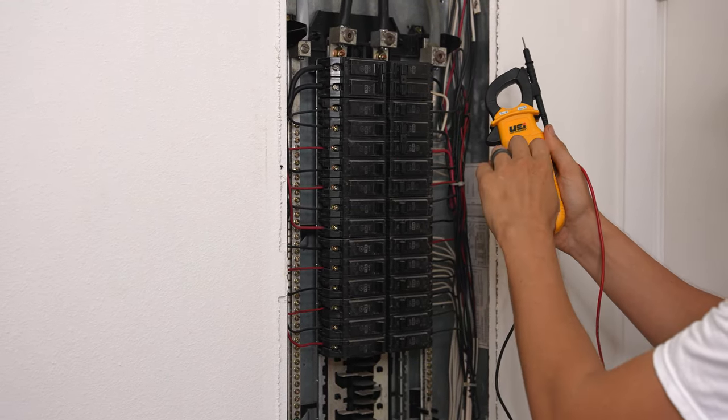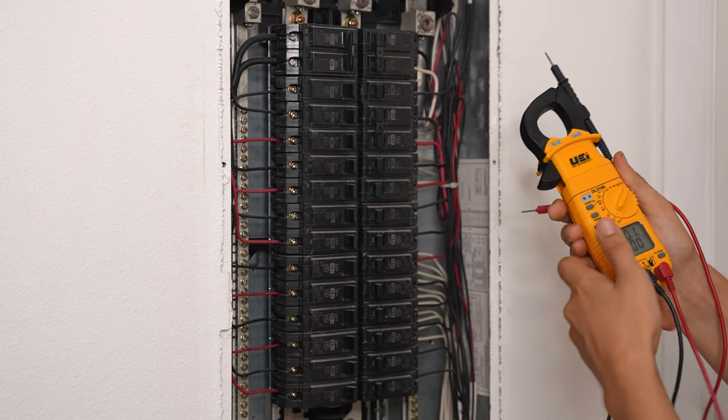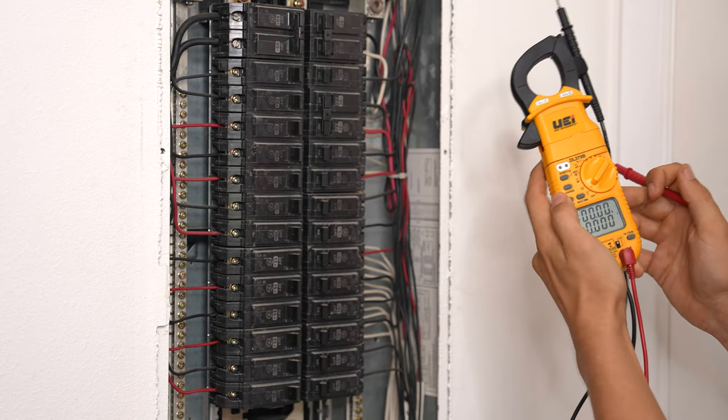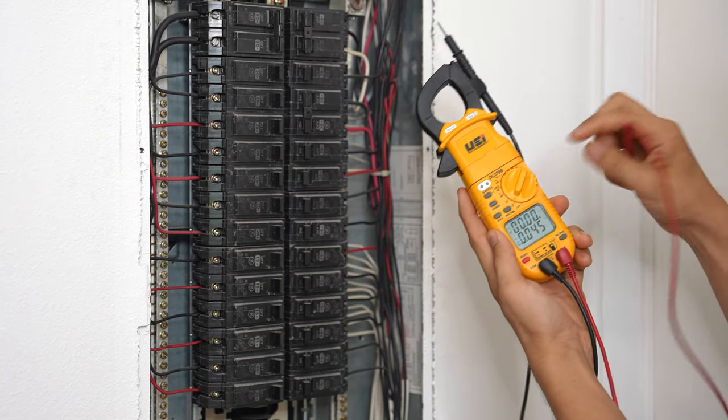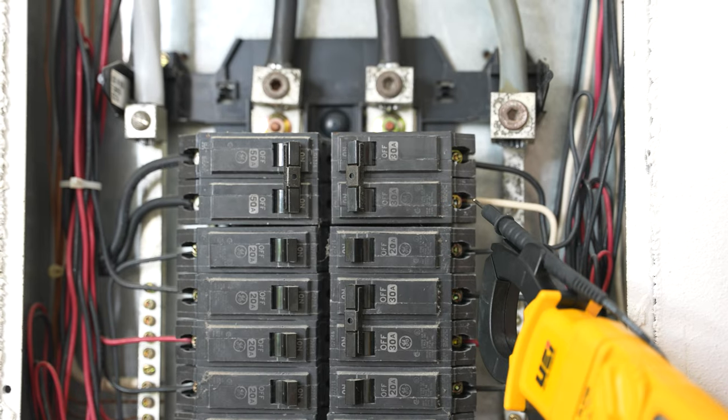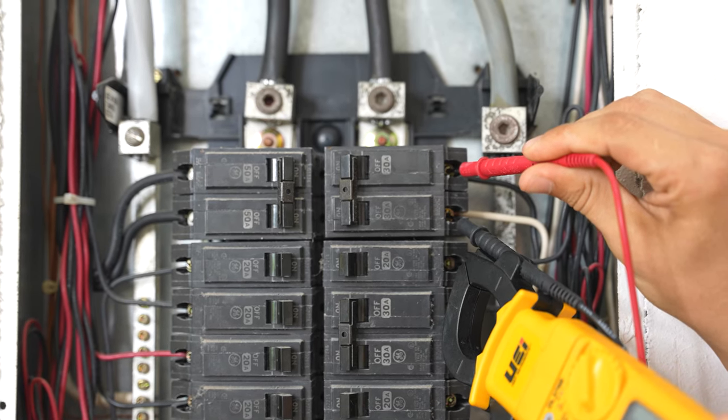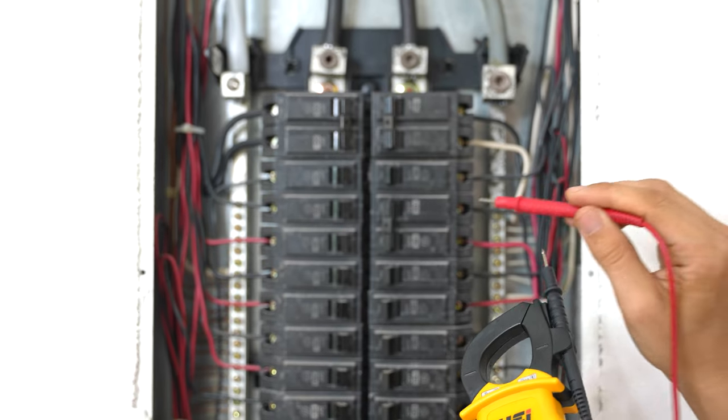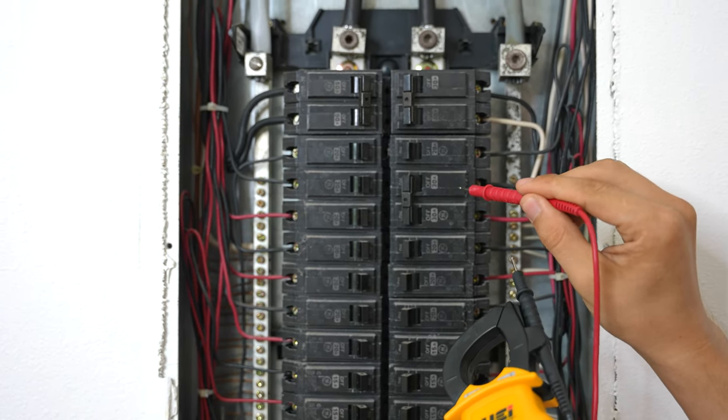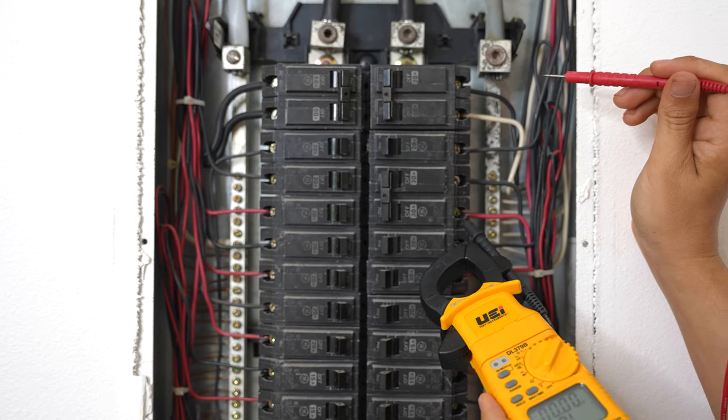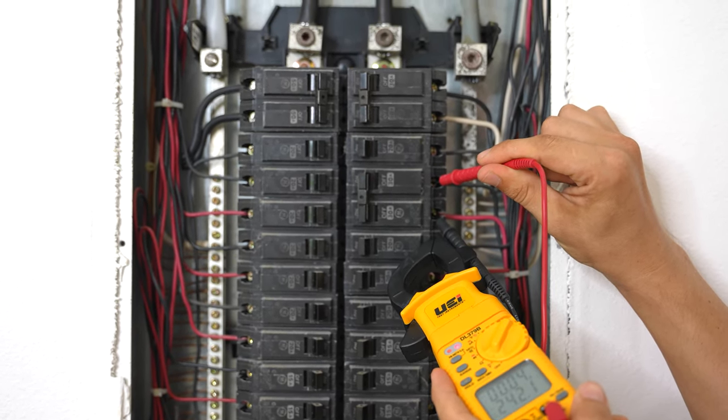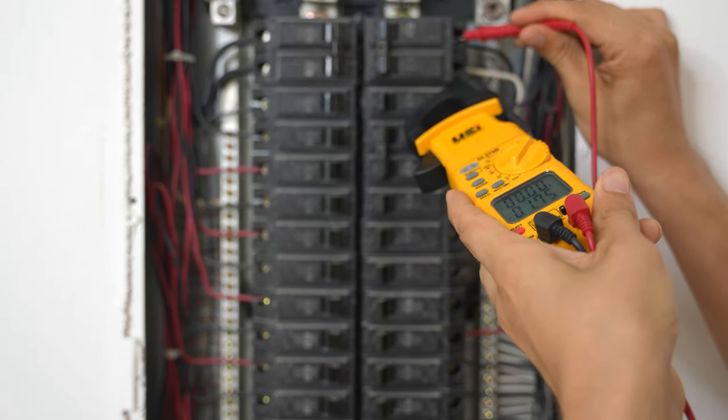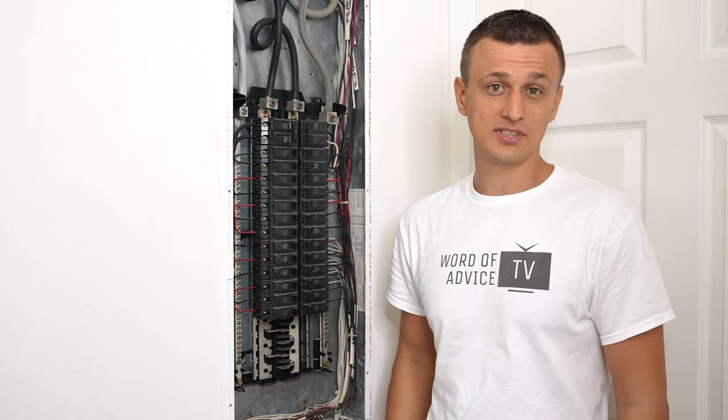So this is my water heater breaker. It's a 30 amp breaker. I'm going to switch my meter to voltage. And electricians recommend using one hand if possible to check voltages. That can be a little bit uncomfortable. So what I like to do is use my meter as my other hand. I just plug one lead into the meter. So I have it set to voltage. And I'm going to check from the two terminals going into this breaker. This is supposed to be 240 volts. And I'm getting zero coming out of it, even though the breaker is on. And this breaker, for example, this two pole breaker is from my dryer, which is also 240 volts. If I check this one, look at that. I do have 242 volts. So 240 here, but zero here, even though they're both on. So at this point, you would turn the power off and proceed with the replacement.